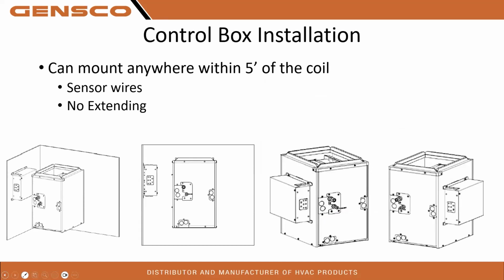This slide here is showing the different orientations of how we can mount the control box. Again, I don't really care where you mount it as long as it's within 5 feet of the coil. You can mount it on the wall, in the coil, on the ceiling, on the floor, mount it in your mother-in-law room. I don't really care, as long as it's within 5 feet because of those coil thermistor lengths. You cannot extend those wires. So what you get is what you get. As long as you're within 5 feet, you're good. Don't try to go further than that.